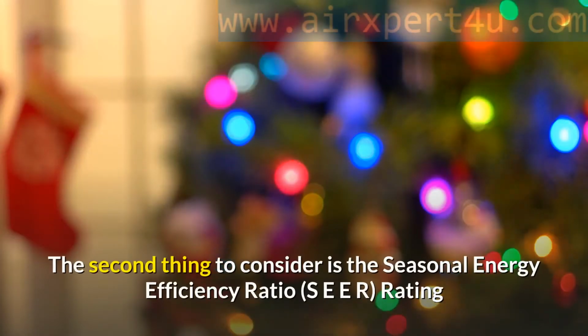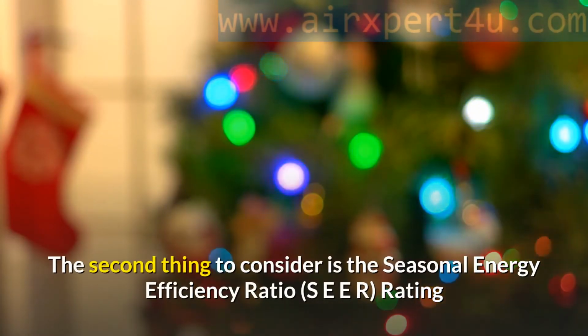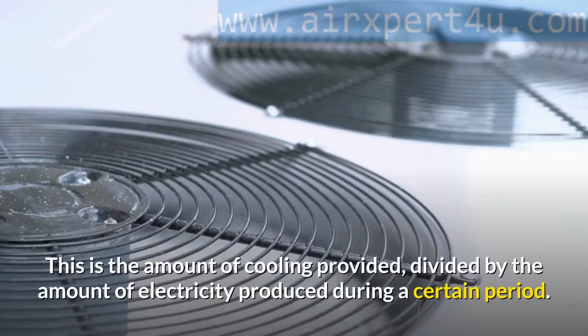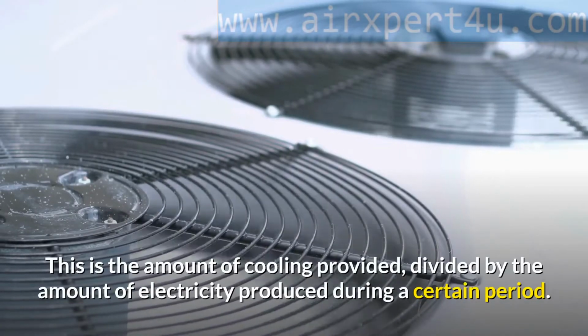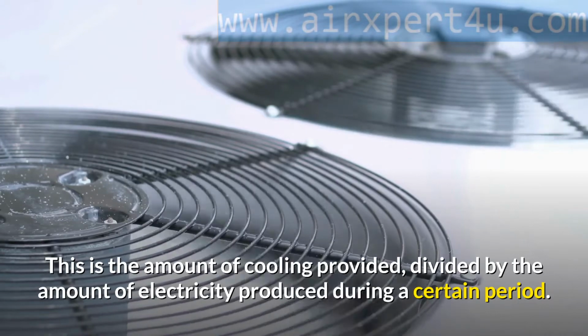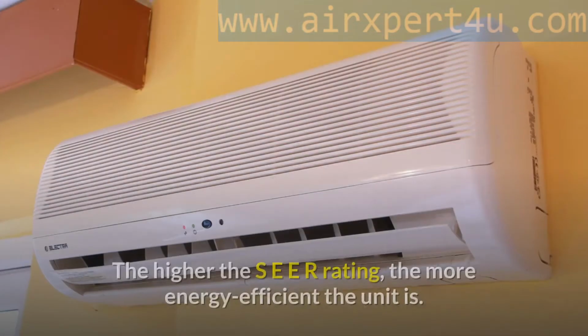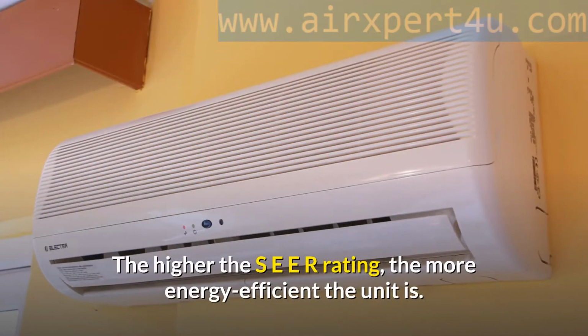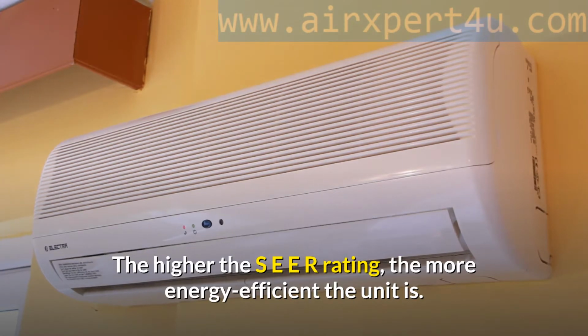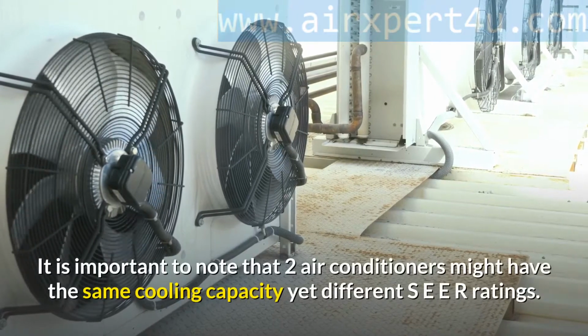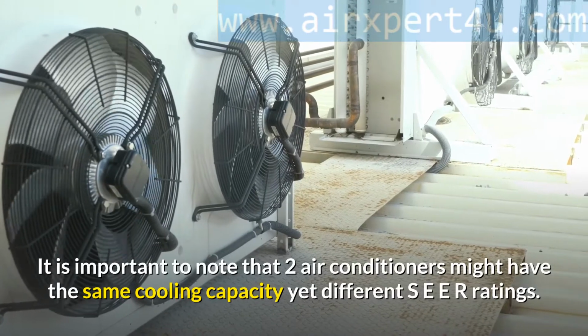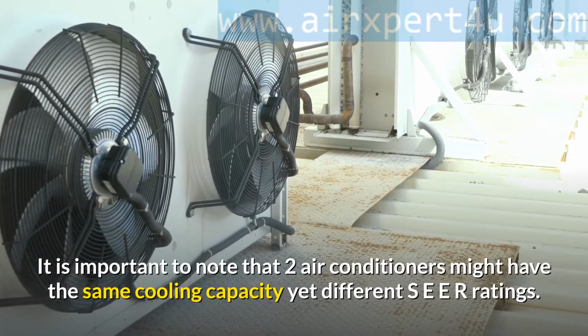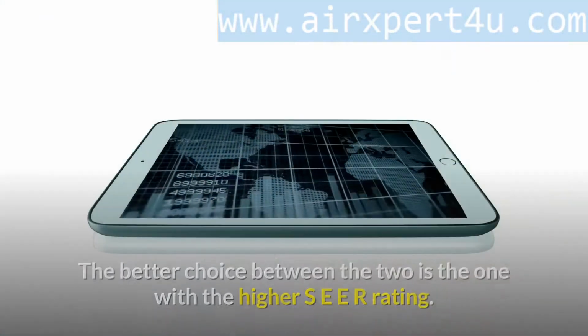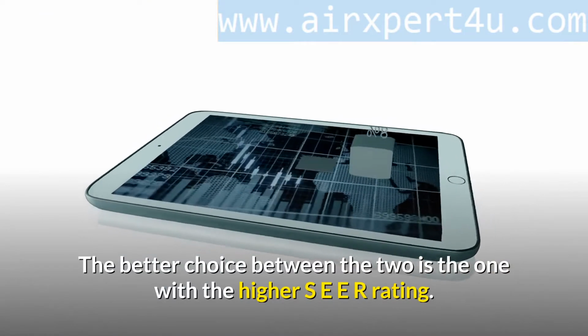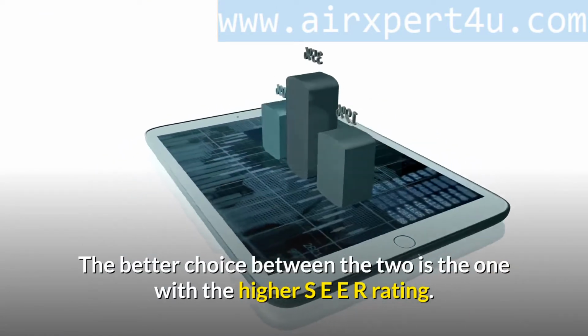The second thing to consider is the Seasonal Energy Efficiency Ratio (SEER) rating. This is the amount of cooling provided, divided by the amount of electricity used during a certain period. The higher the SEER rating, the more energy efficient the unit is. It is important to note that two air conditioners might have the same cooling capacity yet different SEER ratings. The better choice between the two is the one with the higher SEER rating.